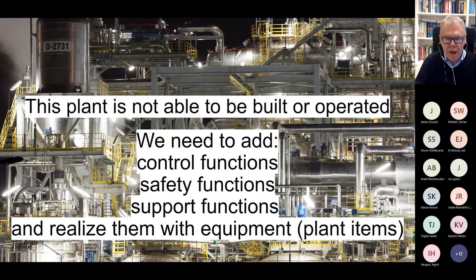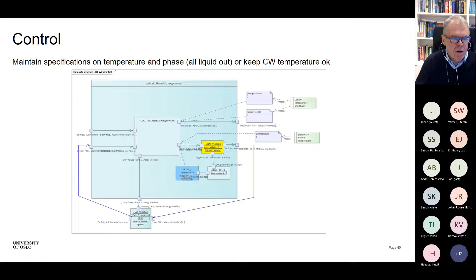So we go in and say we actually have to control temperature and phase of the product out, and we have to limit the cooling water return temperature from the cooling water of this heat exchanger. That means we can postulate that we need a control function, a monitoring function, and a place where we can actually control the water flow rate. So we have this water control function.